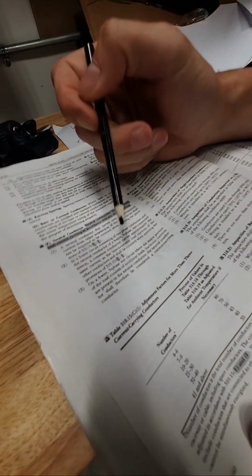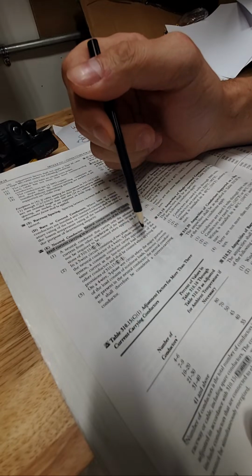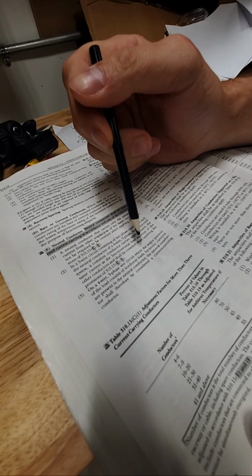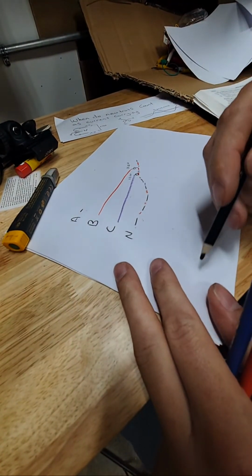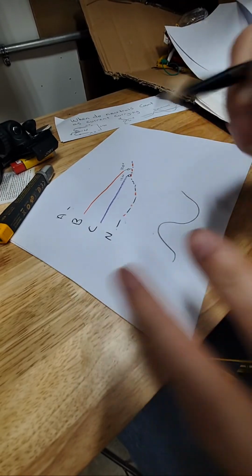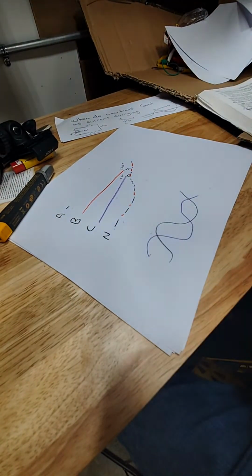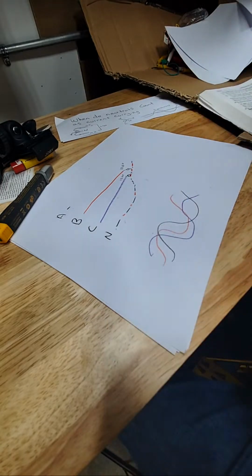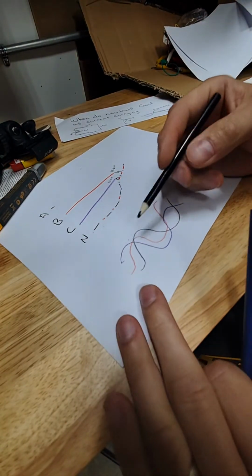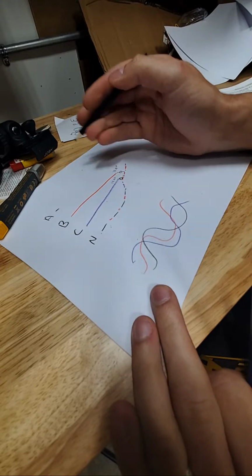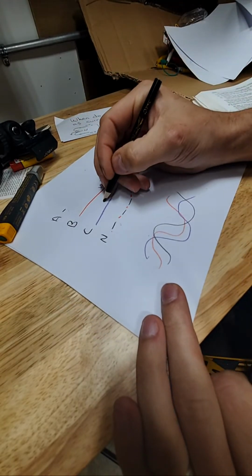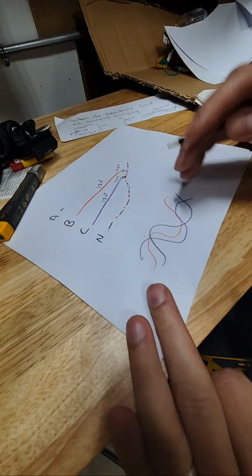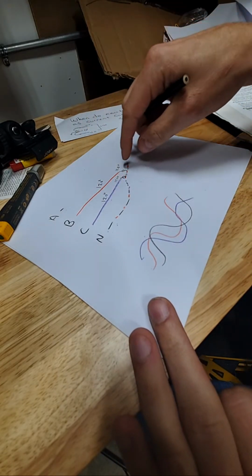It says here, the line to neutral currents of the other conductor shall be counted when applying the provisions. So this is exactly what they're talking about. And the reason for that is because of that sine wave that we showed earlier, where you've got this number going on, right? You got them all. Well, they're not going to be in phase because you're only using 2 of these. So this is at 120 degrees. This is getting kind of technical, but this is why. This is 120 degrees, and they're out of phase. They're not able to cancel the neutral out.